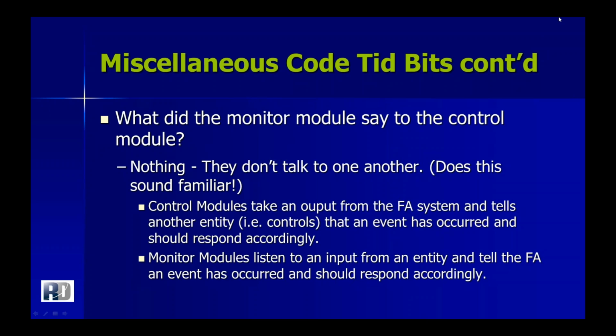But control modules, and the reason that we want to identify control modules and monitor modules is that when we're listening to people out in the field, between the owner or even the contractors, they're throwing around terms so often, and they make them sound like they're synonymous, and they're really not. The control module is taking that output from the fire alarm panel, and it's telling another entity, which could be controls, it could be door hardware, it could be many different things, that an event is occurring in the fire alarm, and the system needs to respond accordingly. Conversely, a monitor module is those remote entities that are sending an input into the fire alarm panel so that the fire alarm panel knows that there is a condition happening outside of the system. It could be an HVAC occupancy signal. It could be other signals, even again from door hardware.